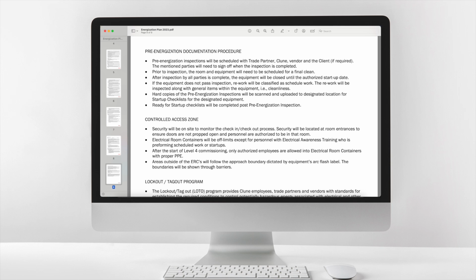Hard copies of the pre-energization inspections will be scanned and uploaded to a designated location for startup checklists for the designated equipment. Ready for startup checklists will be completed post pre-energization inspection. Controlled access zone security will be on site to monitor the check-in, check-out process. Security will be located at room entrances to ensure doors are not propped open and personnel are authorized to be in that room. Electrical room containers will be off limits except for personnel with electrical awareness training who are performing scheduled work or startups. After the start of Level 4 commissioning, only authorized employees are allowed into electrical room containers with proper PPE. Areas outside of the ERCs will follow the approach boundary dictated by equipment's arc flash label. The boundaries will be shown through barriers.